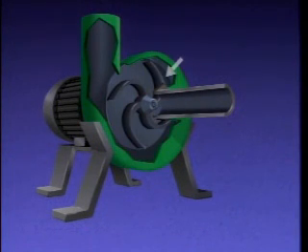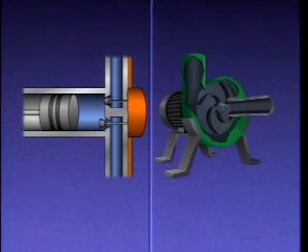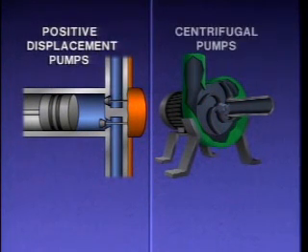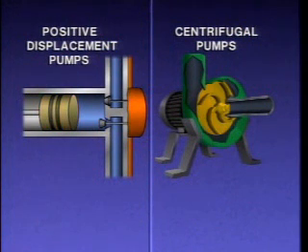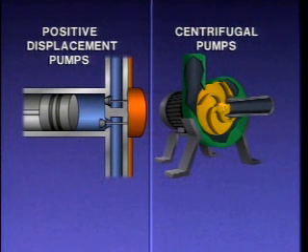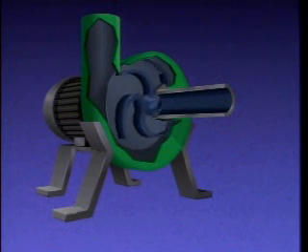Inside the pump, there's a component that physically moves the liquid through the pump, and the type of component used determines the type of pump. Basically, pumps can be grouped into two general categories: positive displacement pumps and centrifugal pumps. A positive displacement pump uses a piston or some other device to push, or positively displace, controlled amounts of liquid through the pump. A centrifugal pump, on the other hand, uses an impeller which creates a centrifugal force to move the liquid. Centrifugal force is the force that develops when something moves or spins in a circular motion. In a centrifugal pump, this force pushes the liquid away from the center of rotation and out of the pump.